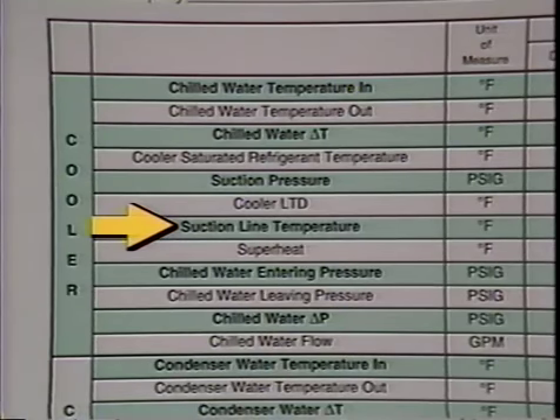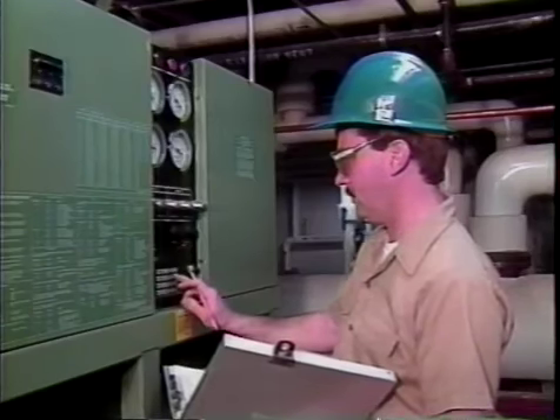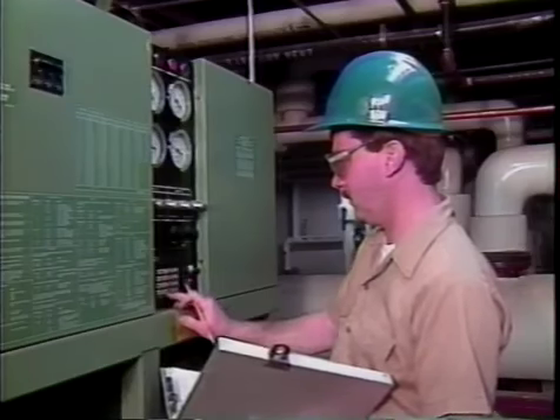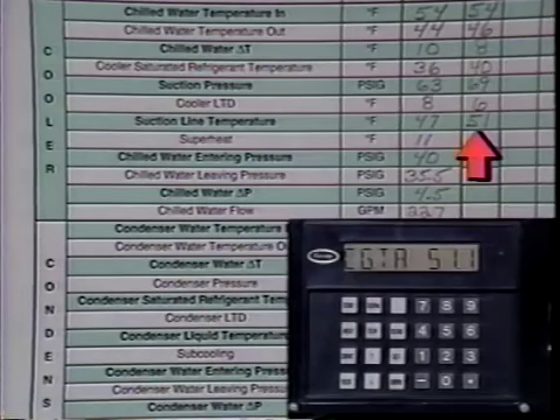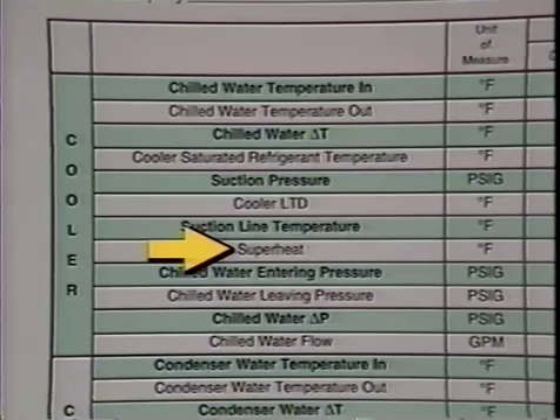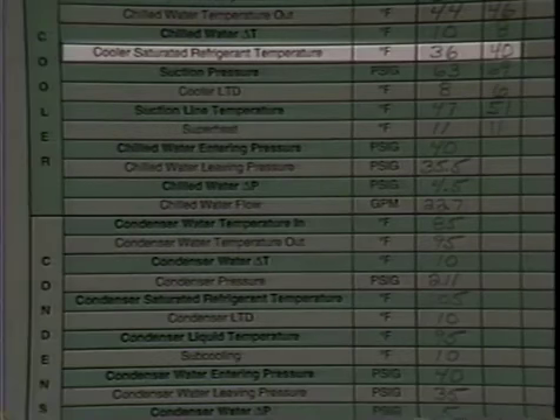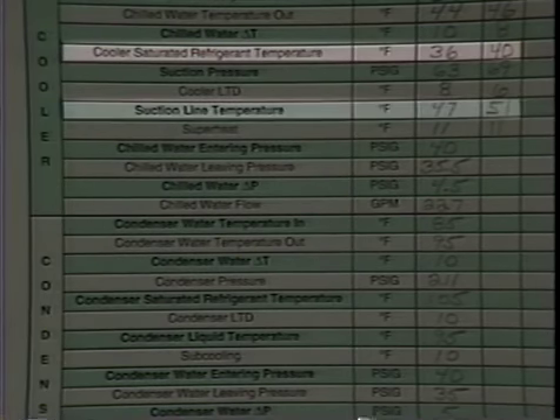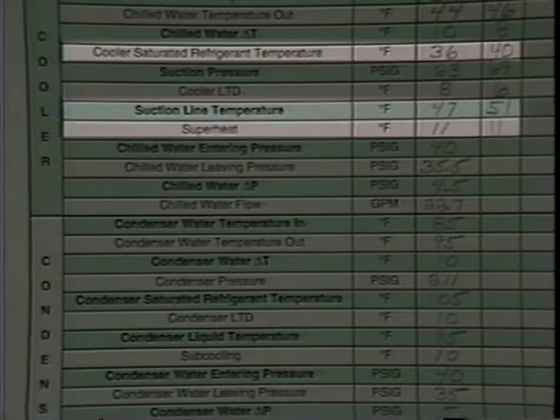Suction line temperature. This measurement is taken on the suction line near the suction service valve. Use a digital temperature probe to take this reading or read it at the control panel display if available. Record this temperature. Superheat. The superheat can now be calculated by subtracting the saturated cooler refrigerant temperature from the actual suction line temperature. On some units, the superheat may be read directly at the control panel display. Record the superheat.